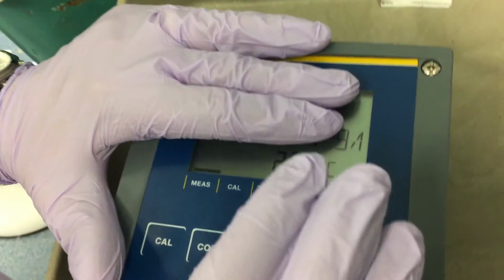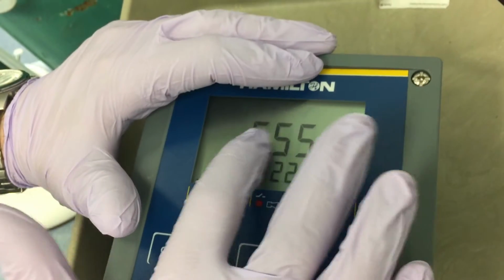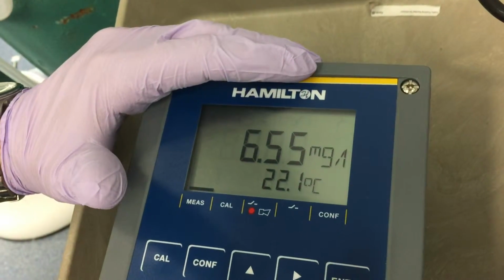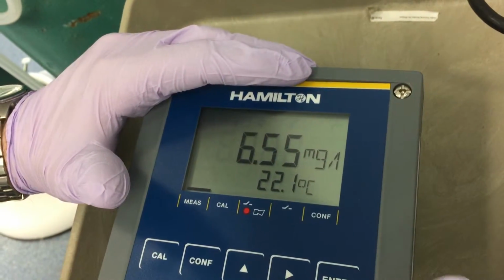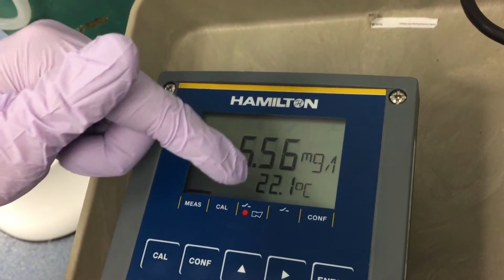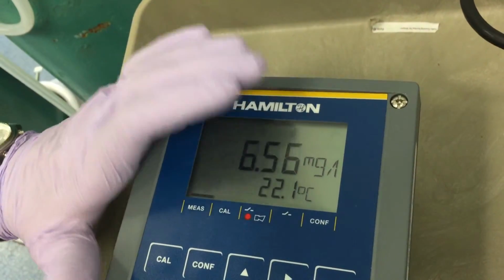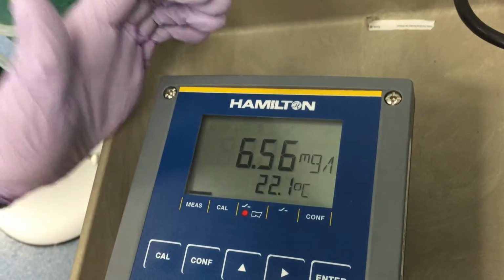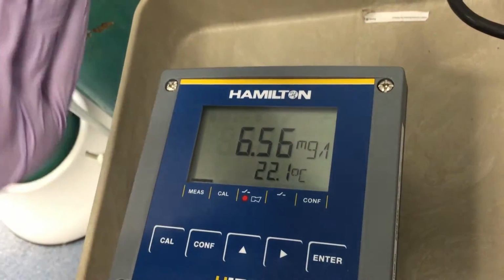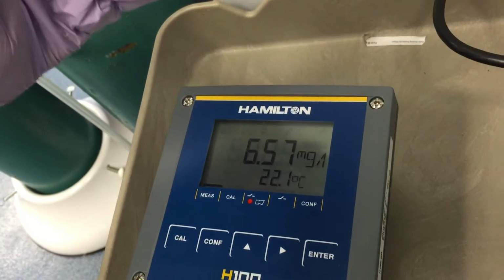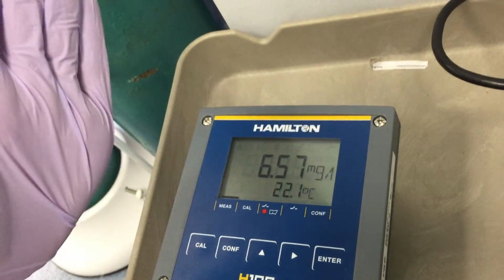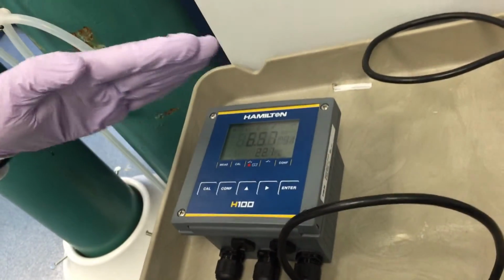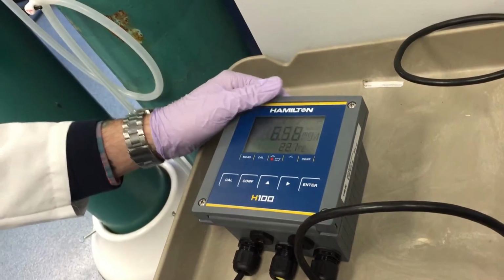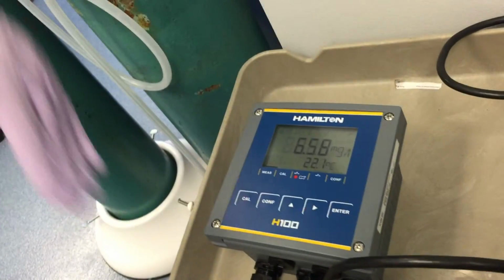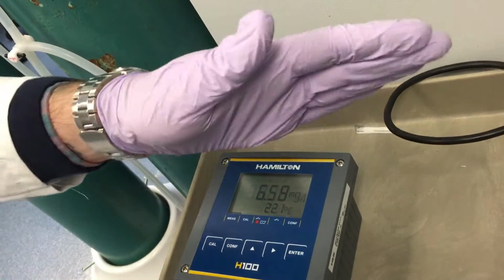You're going to have the current that the probe is reading, and then when that gets to the bottom, you're going to enter that current here, and that's going to be the zero calibration. But you don't want to enter the lowest value that it gets to, because based on my experience, it's going to go really low, and then it's going to climb back up a little bit, and then it's going to level off. You don't want to do it at the very bottom of that trough. You want to capture it where it's leveled off. It's just the sensitivity of the instrument. It goes low and then it settles on what the actual zero calibration is.